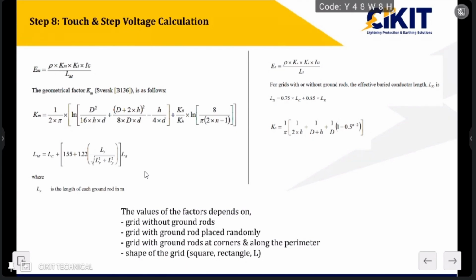So we have calculated the actual step and touch voltages, then we have calculated the value of GPR, then we have calculated the value of IG also. Now we have to calculate what will be the actual step and touch voltage on this particular site conditions. The actual step and touch voltage on this particular site conditions can be calculated by using this formula.